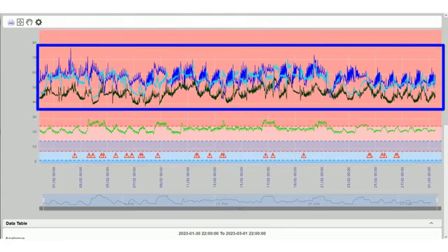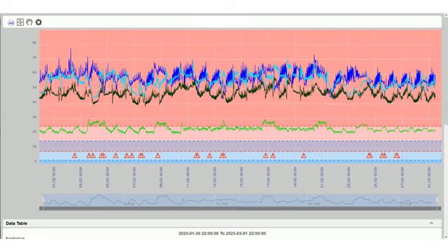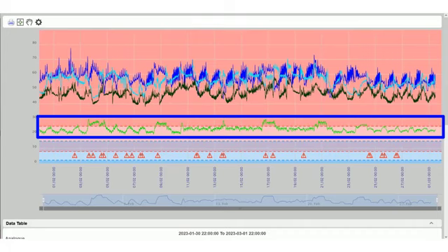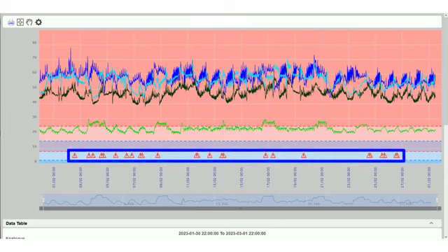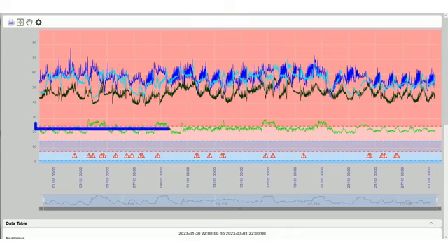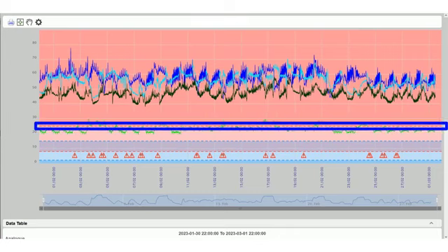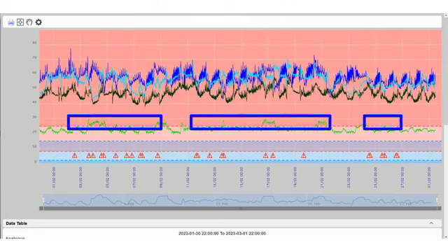Here, relative humidity readings are between approximately 37 and 71%, and temperature readings are between approximately 22 and 28 degrees Celsius. The graph's vertical axis contains a scale of value ranging from 0 to 80. This makes it possible to show ambient temperature and relative humidity readings on the same graph. We also see that a number of alarm events have been logged. With the upper limit for ambient temperature being 25 degrees Celsius, we can see that there were quite a few temperature excursions, all of them marked by alarm events.